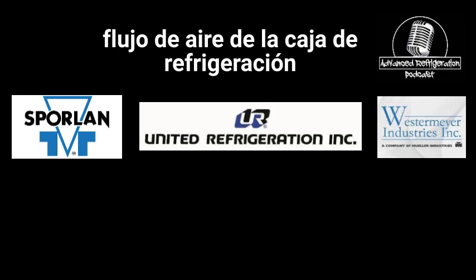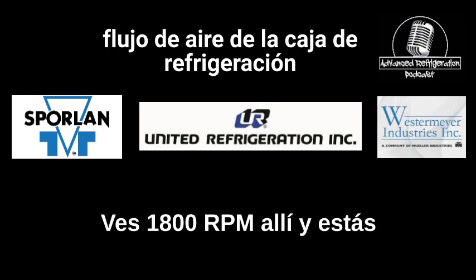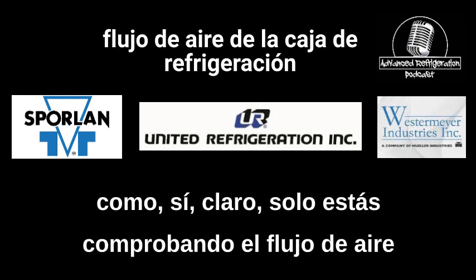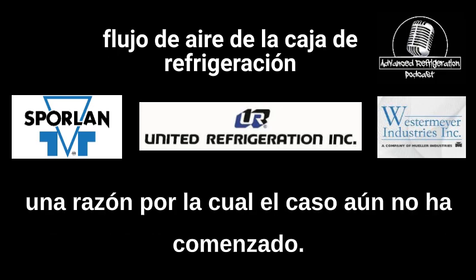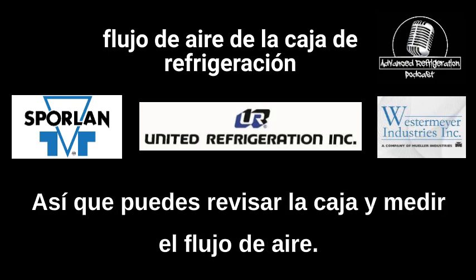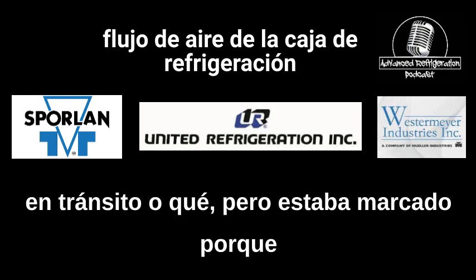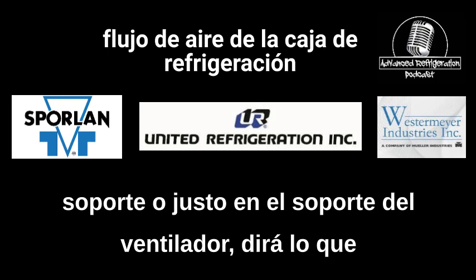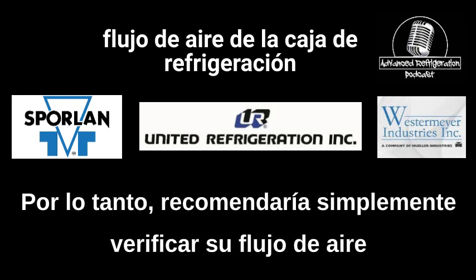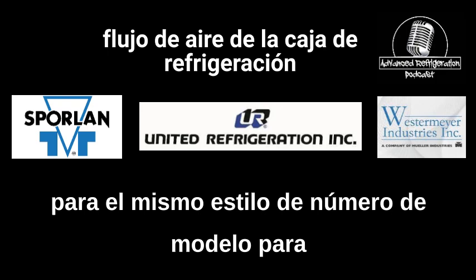Sometimes they don't come programmed properly from some of the manufacturers, and you see 1800 RPM on there, and you're like, yeah, sure. You're just checking the airflow, and then you find out that it's low. And if it's a brand new case, then there's obviously a reason why. The case hasn't even started up yet, so you can go through the case and measure the airflow, and that's what it was. I don't know if it lost its program in transit or what, but they usually have a little sticker around the plenum of the fan bracket, or right on the fan bracket. It'll say what it was originally supposed to be programmed for. So I would recommend just checking your airflow on a startup, just to make sure you basically have all the same RPM for the same model number of the case.